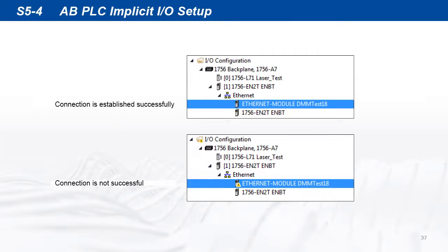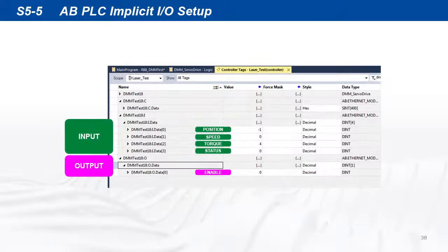If everything is configured properly, the module connection is established. If there are issues with the connection, a warning will be shown. Open the controller tag screen to see the IO data created for the DMM servo drive. We can see the 4 input data blocks and 1 output data block running.